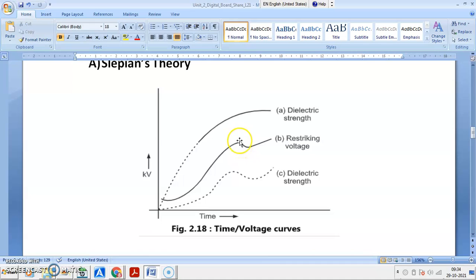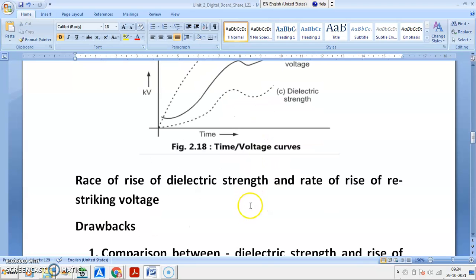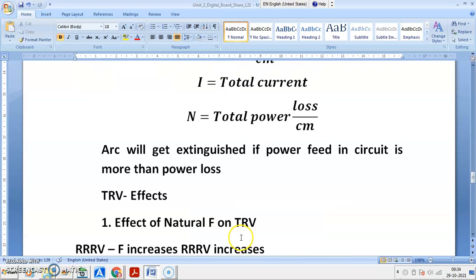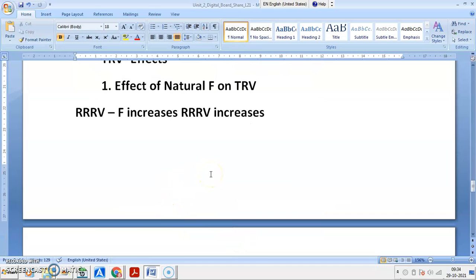लेस. सो इट मे be more than the rate of rise of dielectric strength and it may cause problem in arc extinction. म्हणजे arc may not get extinguished. So breaking capacity of circuit breaker reduces as natural frequency increases. So that is the effect of natural frequency.